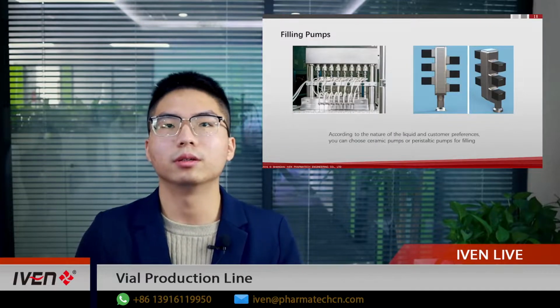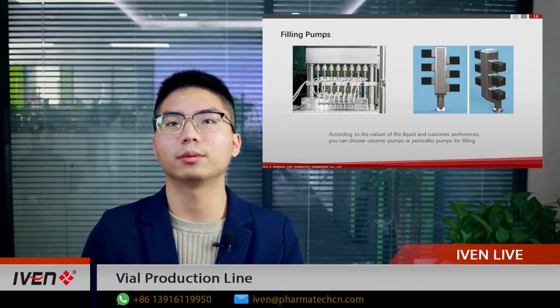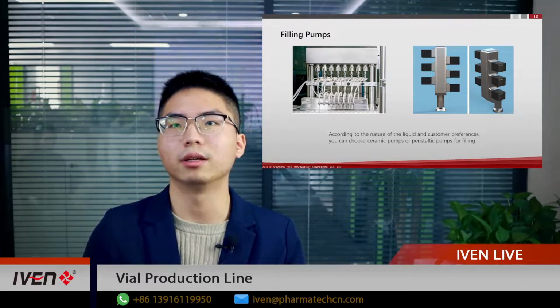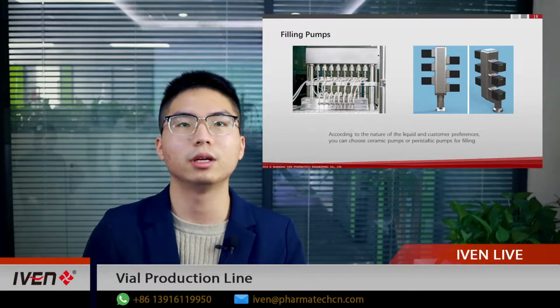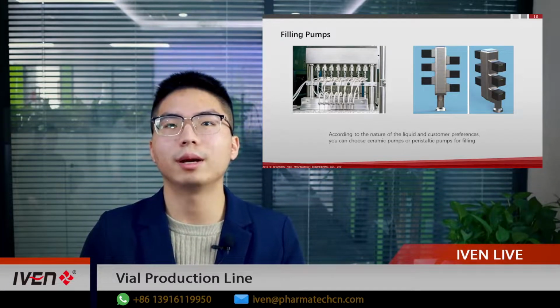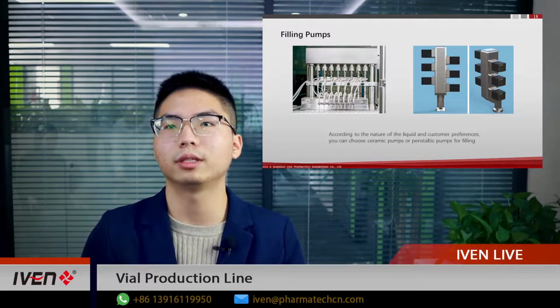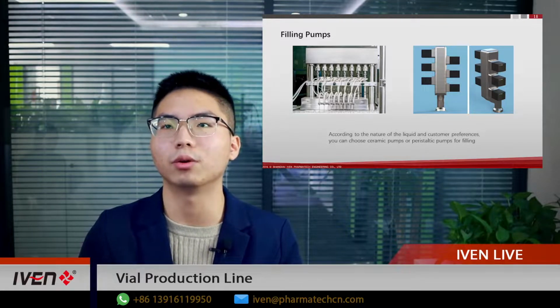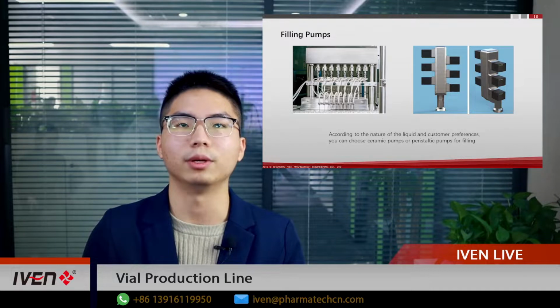Through the rotary table, vials will be delivered to a filling station. For filling pumps, you can choose ceramic pumps or peristaltic pumps for filling according to the nature of the liquid and your preferences. After filling, vials will be delivered to a stoppering station. That is a rubber stopper locker, which can achieve no vial, no stopper.